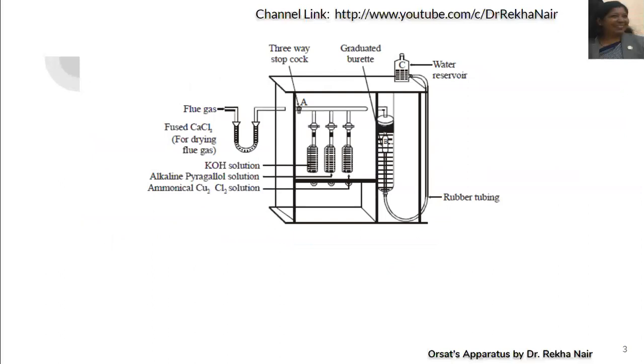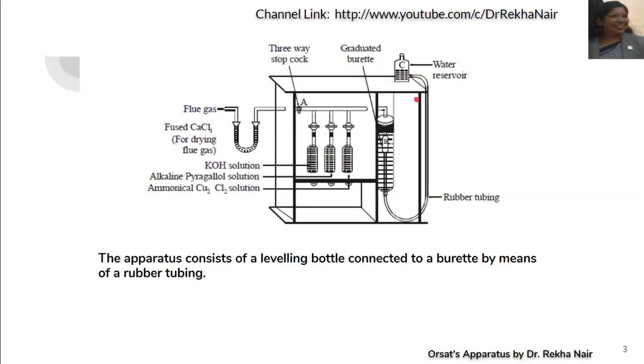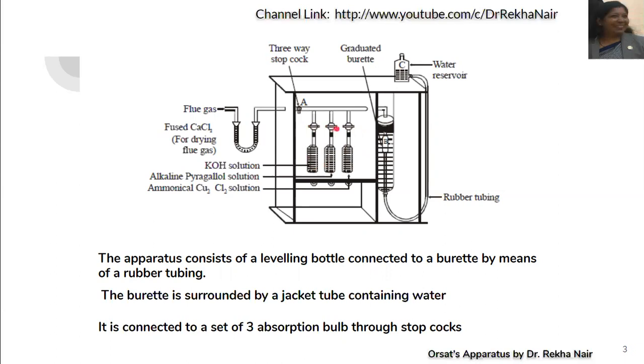This is the equipment — this is the Orsat apparatus. In this Orsat apparatus, it consists of a leveling bottle connected to a burette by means of rubber tubing. By changing the position of the water reservoir, we can change the level of water present in the burette. This burette is surrounded by a water jacket tube containing water. It is connected to a set of three absorption bulbs, and all three bulbs have different stopcocks.